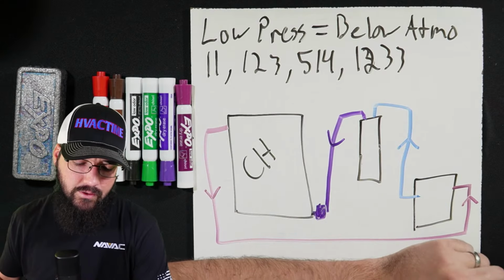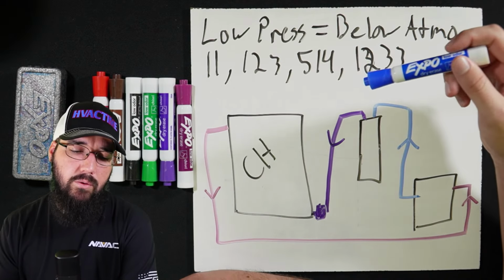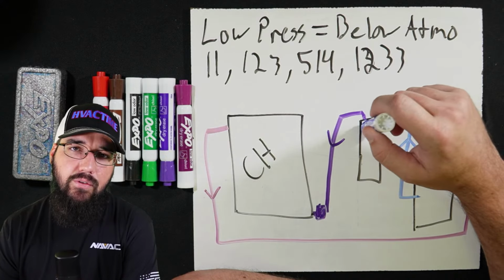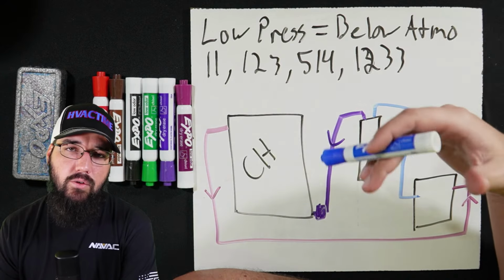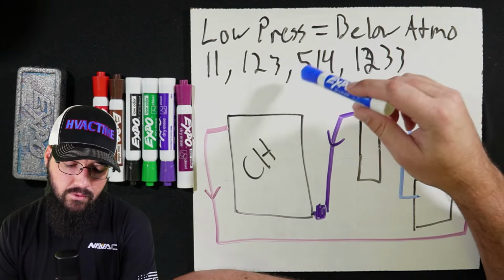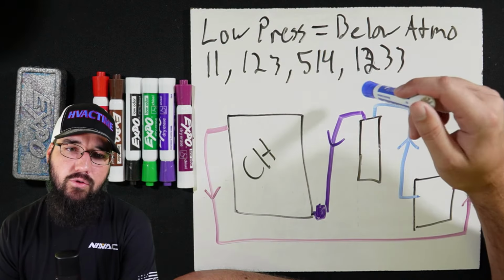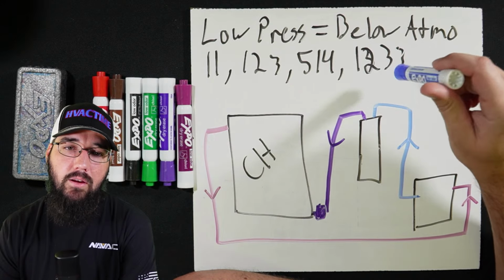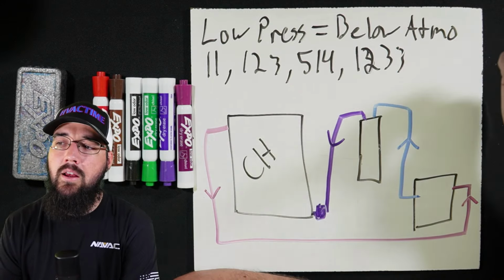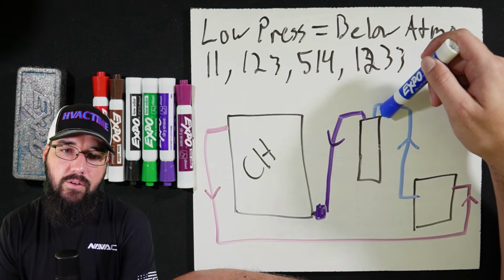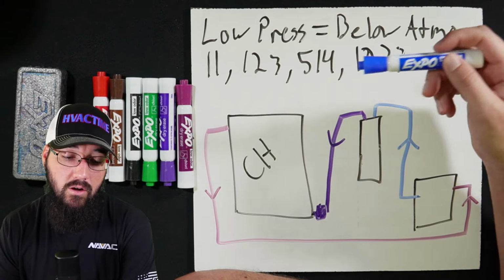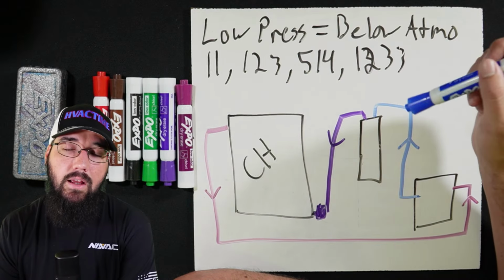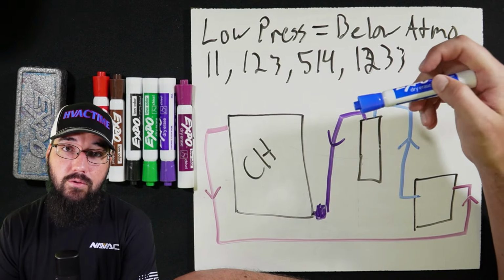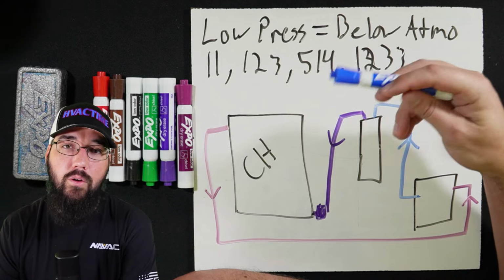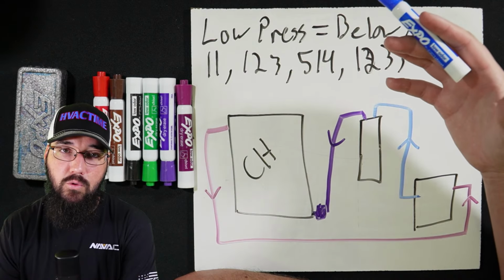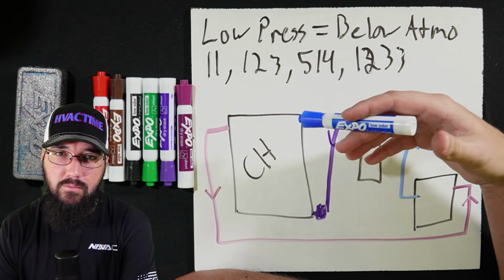There are other methods to this, by the way. One would be what's known as a gravity feed, and I've done this. A lot of your low pressure refrigerants will come in drums. They won't be a recovery cylinder. Like if you buy 134A, you're going to get it in a cylinder like this. But you may buy a drum of 123, and it comes in a literal drum, like an oil barrel, usually a smaller size, like in a 100-pound increment or something.